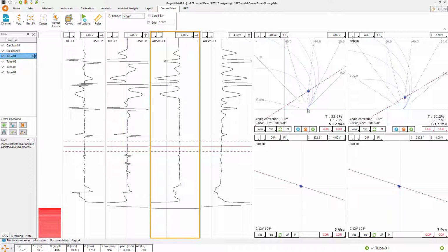But since you have that a lot in the heat exchanger, most people have come to just renormalize the signal when the change is not too high. So when we do that, it brings back the signal correctly and you can size, but it also induces an error in the sizing. So depending on what you want to do and depending on how much the signal has rotated, there are various options here with the new model.